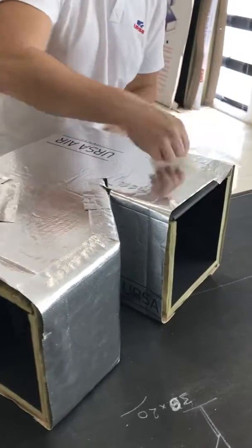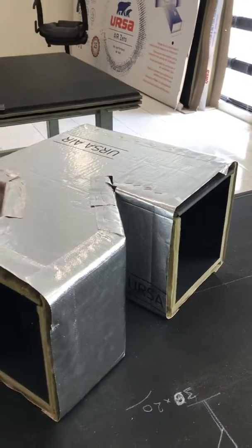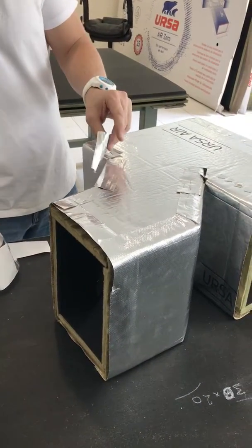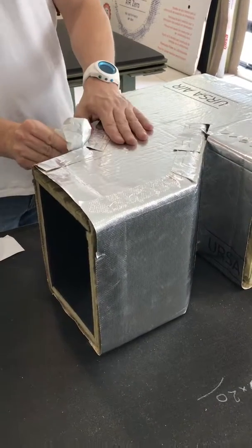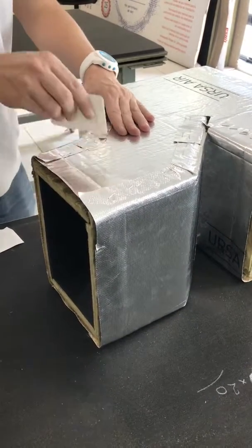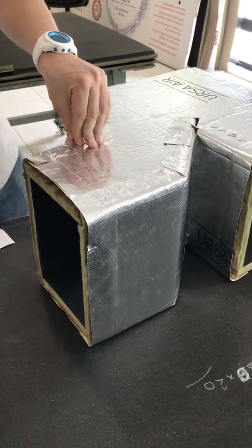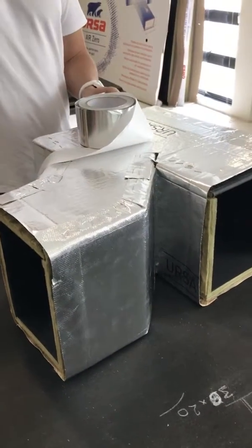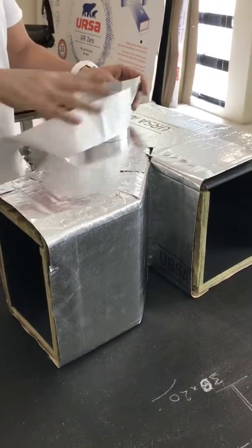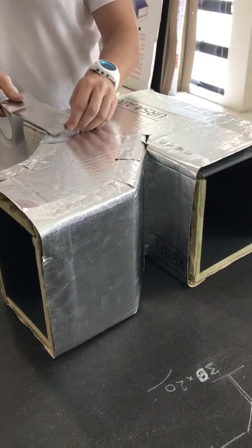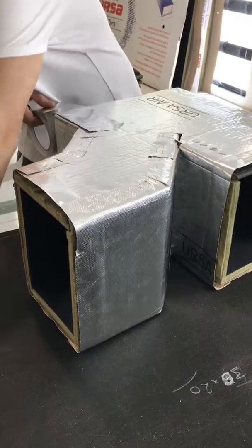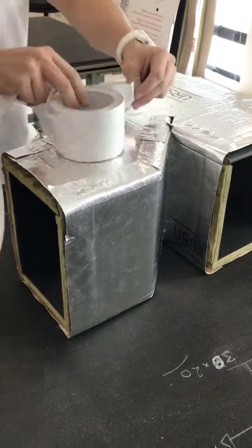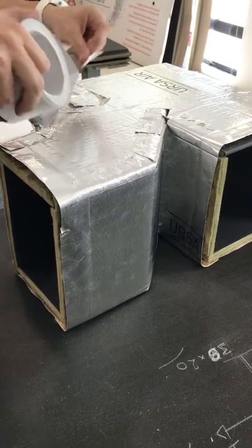What do you think? Questions? Okay. And the level of airtightness is level D. The leakage always depends on the pressure, and it is always a curve that depends on the pressure. It is an air leakage. Okay. You can see that this is one of the more airtight systems that you can find, but you can test it. We have tested according to that standard, and it is level D.